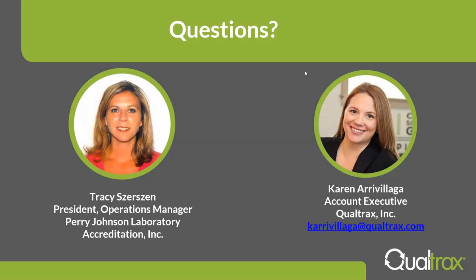Okay, so the standard requires that you come up with the criteria, so I would recommend looking at that. The COA is helpful, where you can take a look to make sure you're getting the information you need. Remember, that section talks about communicating with your customers about what you want. For example, say you use the uncertainty for your test and you're getting something calibrated, but that impacts your uncertainty. You need to make sure you ask them for the uncertainty. So that's the criteria you're talking to them about, and you're confirming that the report they're giving you is appropriate for what you need once you get it. But during the contract review and discussion, you are responsible for trying to clearly communicate what you want from them.